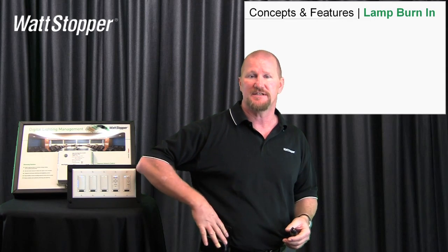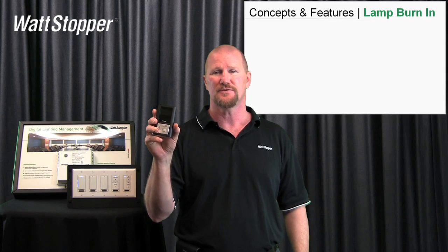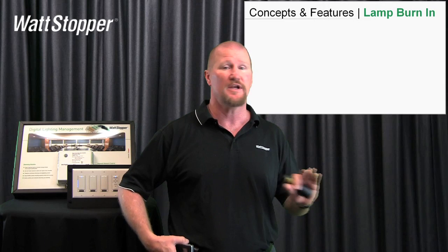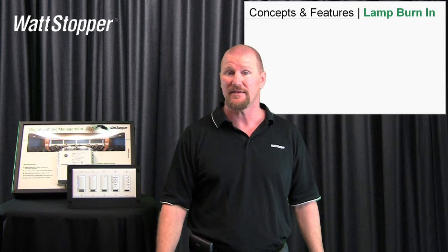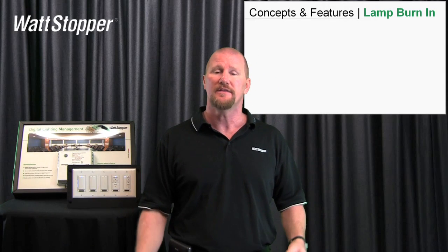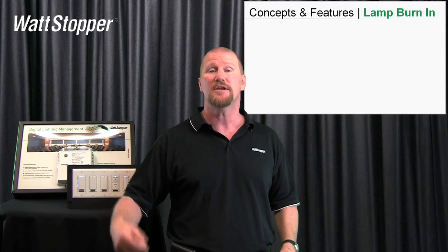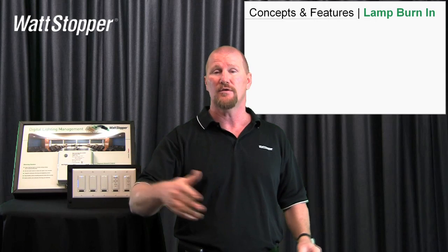You'll set the burn-in using the LMCT100 — our handheld wireless configuration tool. You'll pick the load you want, set the burn-in, and those lights will stay on for the duration, whether 12 or 100 hours. Be aware that occupancy sensors and switches won't turn the lights off during burn-in — the lamps must burn continuously throughout the burn-in period. If you need to stop it, you can use your LMCT100 to stop it, but you can't restart it; you'll have to start over because the burn-in hasn't been successful.